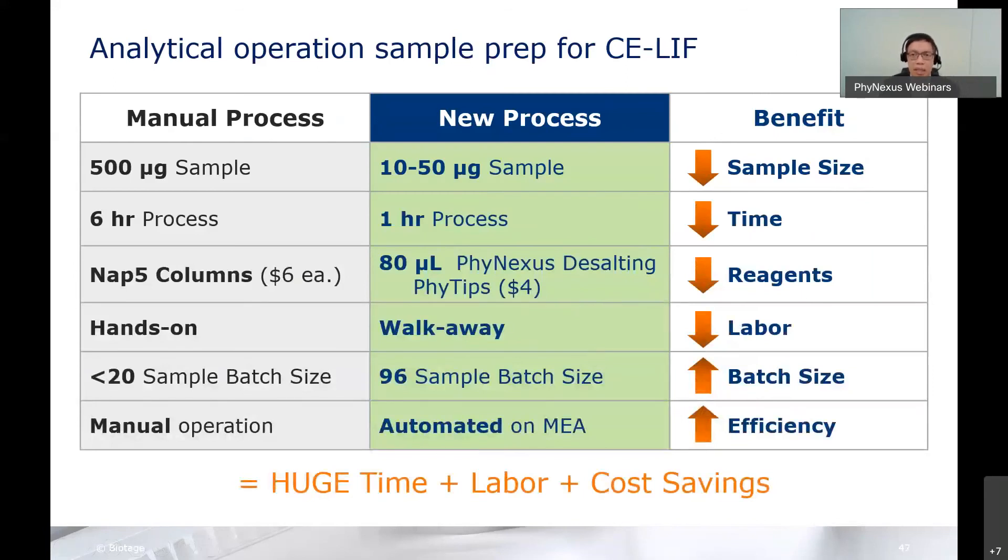This is a real-world example of a CE-LIF assay that we installed for our customer. In the manual process, because we could do smaller volumes, we were able to reduce the sample volume. Reduce the run time from 6 hours to 1 hour. The price is approximately the same based on Nap-5 column and the PhyTip column. But what we get is hands-off automation. We can process up to 96 at a time and have full automation. This is on the MEA; eventually, this was transferred over to a Beckman FX. Lower sample volume, lower run time, smaller amounts of reagents, less labor time, increased batch size, and increased efficiency.